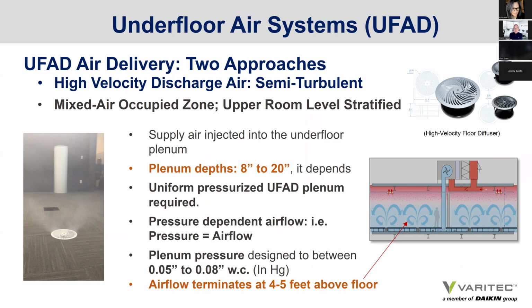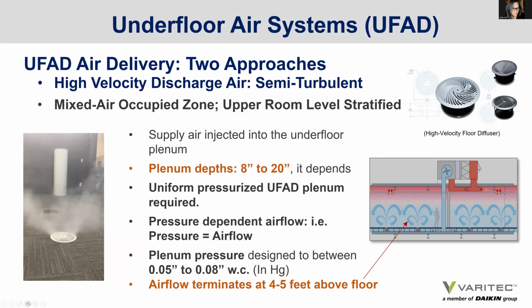So a high velocity discharge semi-turbulent diffuser injects air at a high velocity to create a mixed air environment in the space. The amount of flow through these diffusers is dependent upon the plenum pressure. Airflow rates are dependent upon plenum pressure. To give you an idea, let's have a look at how that air in a semi-mixed condition is injected into the space. You can see the high velocity discharge profile of the air that stops at about 5 feet because it's creating a mixed air condition within the occupied zone.